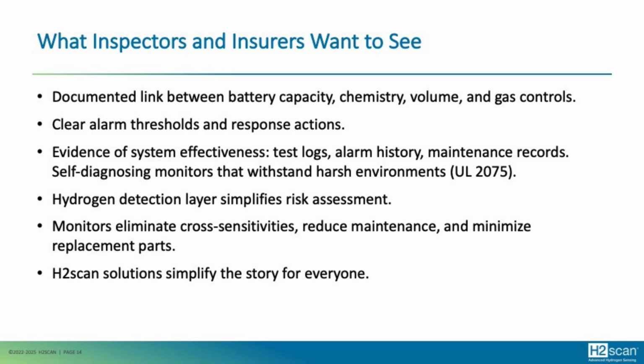And also to choose sensors that eliminate cross sensitivities and are specific to the gas you're trying to monitor. So in this case, hydrogen sensors can also detect a lot of other gases if they're just a general gas sensor. But with, say, for instance, the H2scan sensors, they cannot detect other gases. They are specific to hydrogen. So you can expose them to CO, you can expose them to other gases, solvents in the facility, and it won't react because it's not hydrogen.